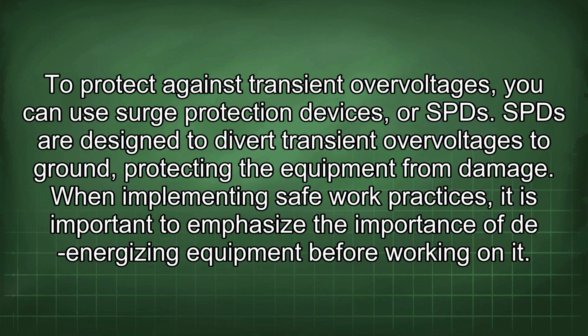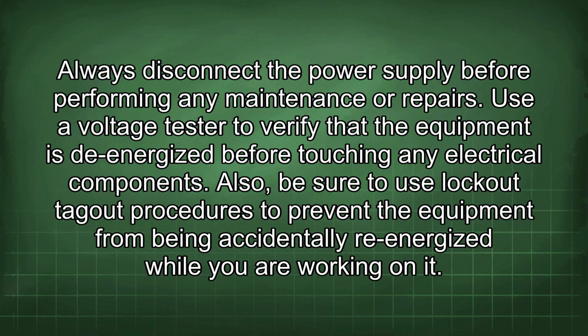To protect against transient overvoltages, you can use surge protection devices, or SPDs. SPDs are designed to divert transient overvoltages to ground, protecting the equipment from damage. When implementing safe work practices, it is important to emphasize de-energizing equipment before working on it. Always disconnect the power supply before performing any maintenance or repairs. Use a voltage tester to verify that the equipment is de-energized before touching any electrical components.